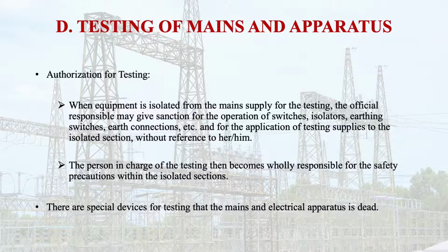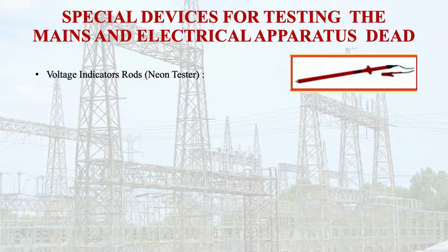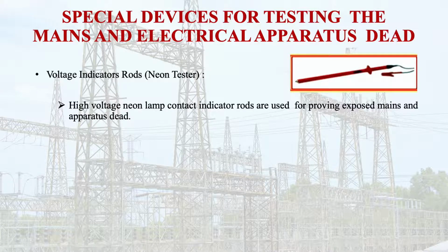So there are special devices for testing that the mains and the electrical apparatus are dead, that is, not energized. We are describing them briefly. So what are these safety devices? The one device is the voltage indicator rod, which is also called a neon tester. High voltage neon lamp contact indicator rods are used for proving the exposed mains and apparatus dead.